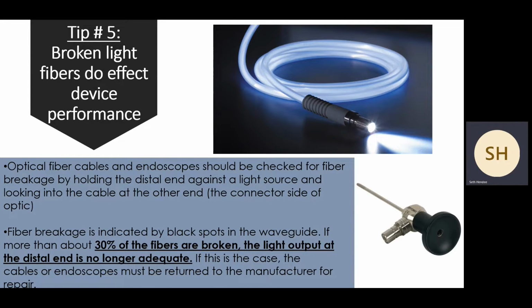Okay, let's talk about broken light fibers. This is one that I love and that I hate because it's actually something that's very simple to do, yet difficult to quantify. Okay, so tip five is broken light fibers do affect device performance. Optical fiber cables and endoscopes should be checked for fiber breakage by holding the distal end against a light source and looking at the cable at the other end. So that's actually quite simple.